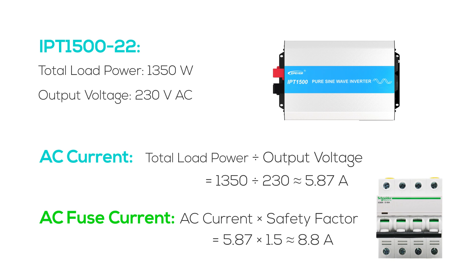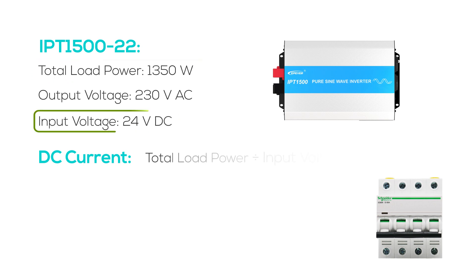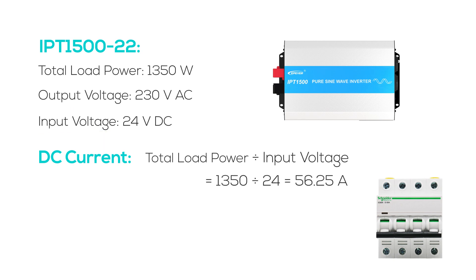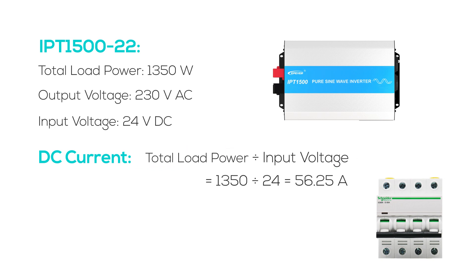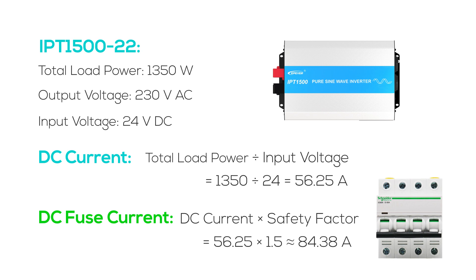Note that when calculating the AC fuse current, the safety factor for copper conductor can be chosen within the range of 1.3 to 1.5 based on actual conditions. On the DC side, with load power at 1350 watts and system voltage at 24 volts, the DC current works out to 56.25 amperes — total load power divided by input voltage. For the DC fuse, we recommend one that can handle 84.38 amperes. For DC circuits, select a safety factor for copper conductor between 1.5 and 2, guided by specific application conditions.